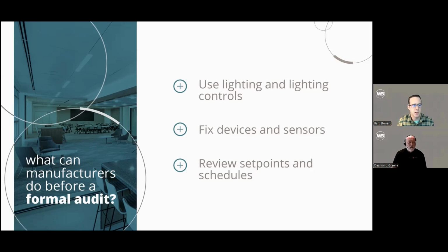The industry doesn't recommend that anymore. ASHRAE doesn't recommend that anymore. No. The equipment manufacturers, you ask Dell, Dell's not going to tell you to maintain the servers at 65 degrees. They're going to tell you to maintain the servers somewhere between 70 and 80 degrees. So raise that up so that it just matches what the rest of your space is doing, and then you don't have those systems trying to fight each other, with this system in cooling while this system's in heating. And you can get a lot of return just by hitting up on that thermostat a couple of times.